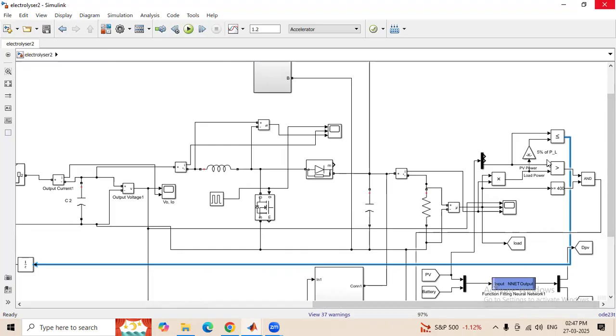The battery energy storage system will provide charging when the power is higher than the load power and the voltage is higher than 400 volts. It will be discharging when any of these conditions are not met. Similarly, the fuel cell will be connected only if the PV power is less than 5% of the load power.